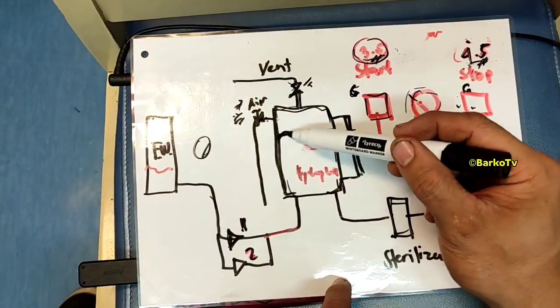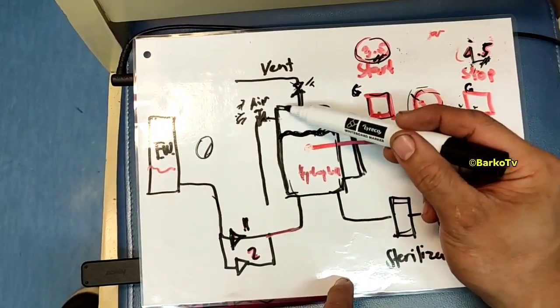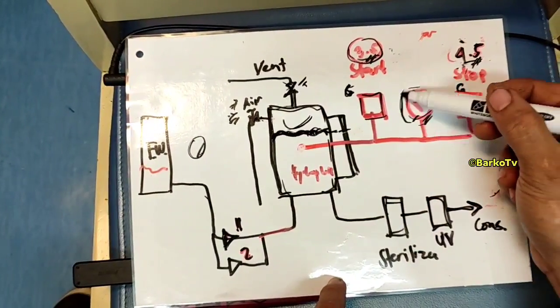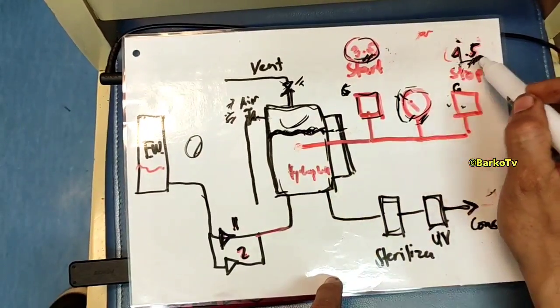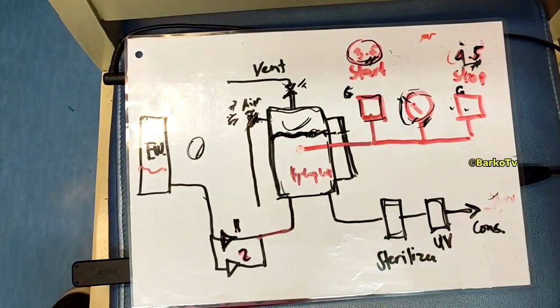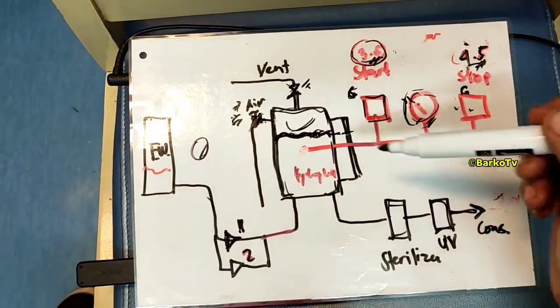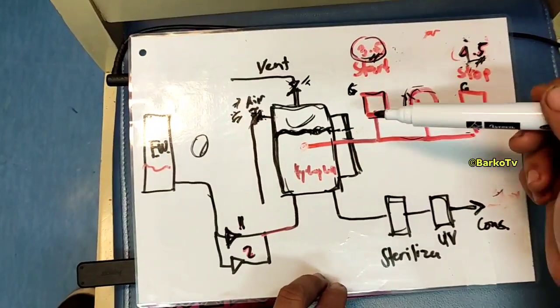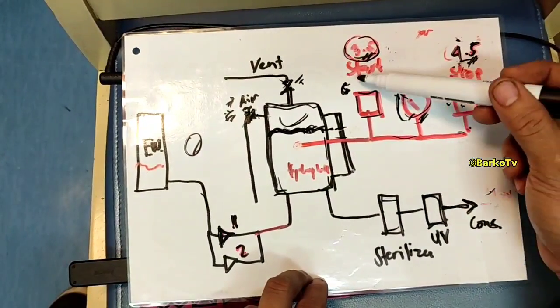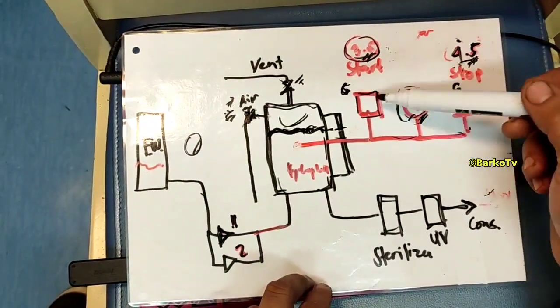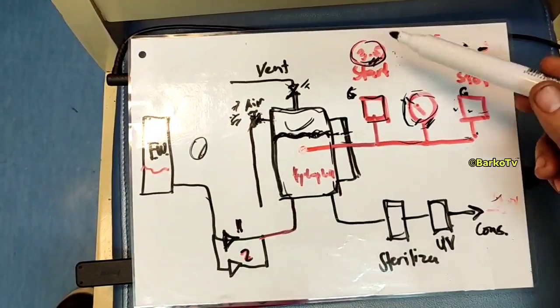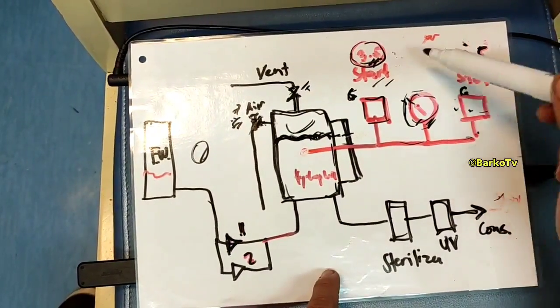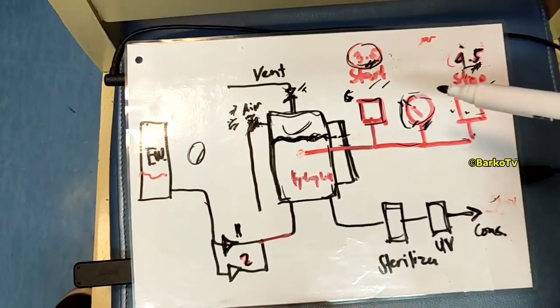Stop is set at 4.5 bar — three-quarters of water, then the rest is air. Build up pressure from zero to 4.5, stop, and then close the air valve. This red line indicates the pipe for the pressure switch. We have two pressure switches: start at 3.5 bar and stop at 4.5 bar.